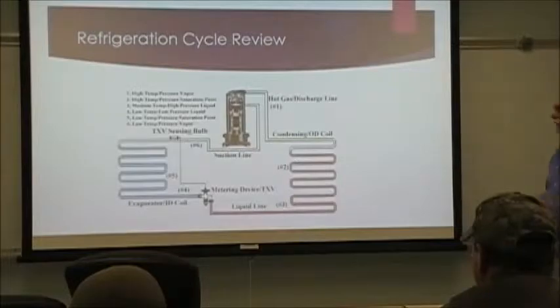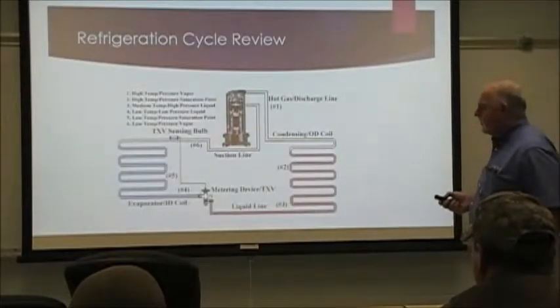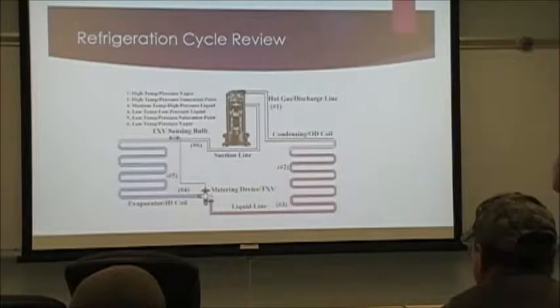That's the main purpose of controlling superheat, is to make sure that there's no liquid coming back to the compressor, because we don't want to damage that.